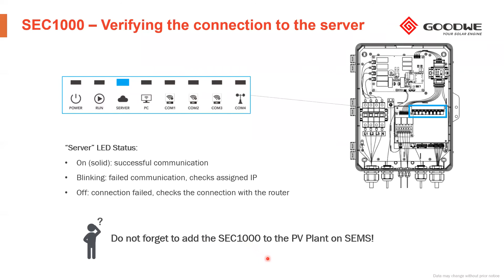Of course, don't forget to add the SEC1000 to the PV plant on SEMS. Otherwise, we cannot monitor the load, we cannot monitor the inverters, etc. So we need to add the inverters and the SEC1000 in our PV plant. If we see in our SEMS portal something like that, we can say that something is wrong. And here, for sure, it is related with the CTs. So we need to check maybe the location, probably the location, and the direction of the CTs. Because the normal view is like this.